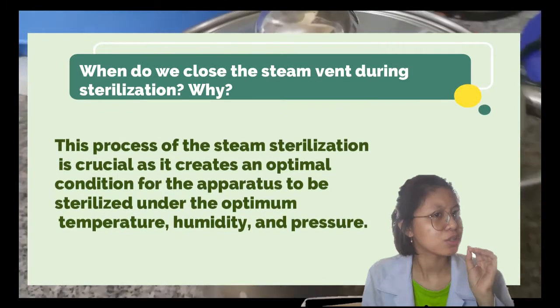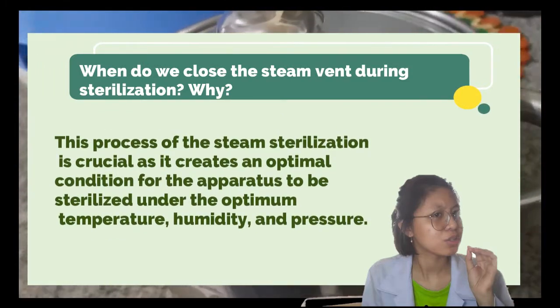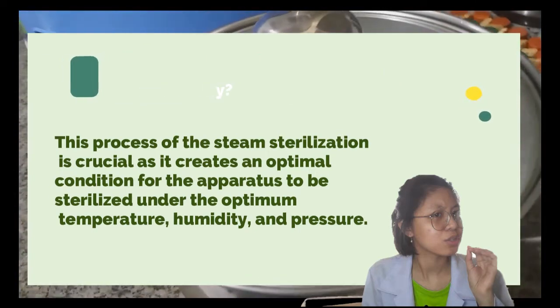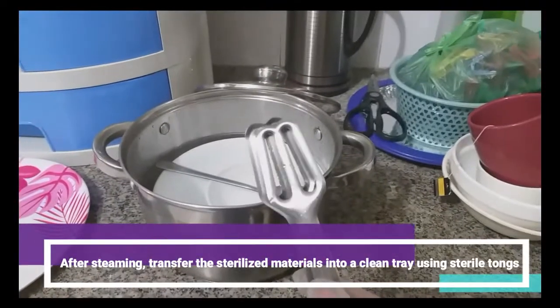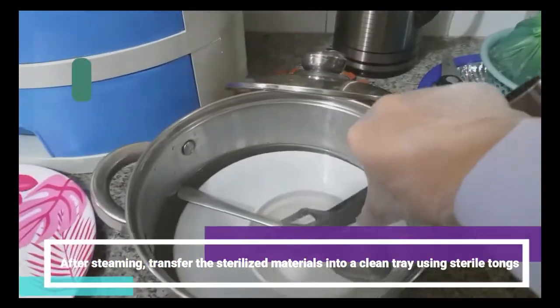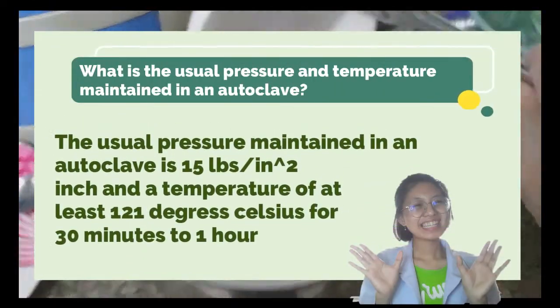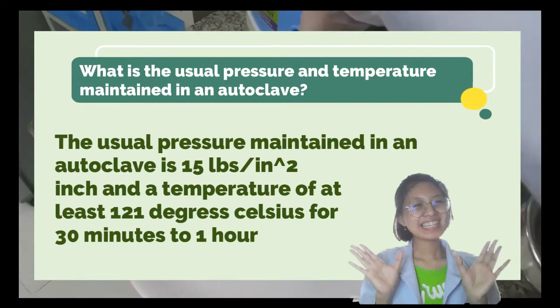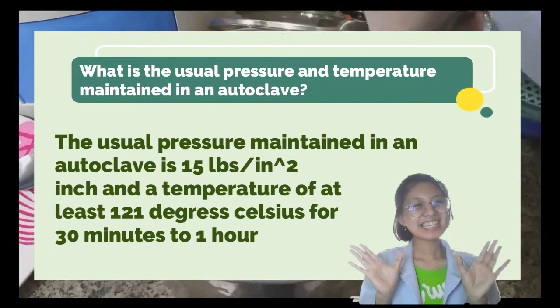This process of steam sterilization is crucial as it creates an optimal condition for the apparatus to be sterilized under the optimum temperature, humidity, and pressure. The usual pressure maintained in an autoclave is 15 pounds per square inch and a temperature of at least 121 degrees Celsius for 30 minutes to 1 hour.